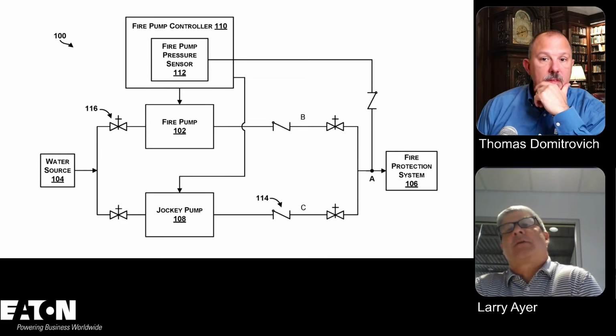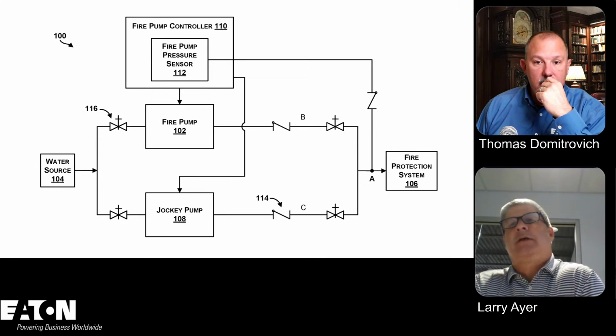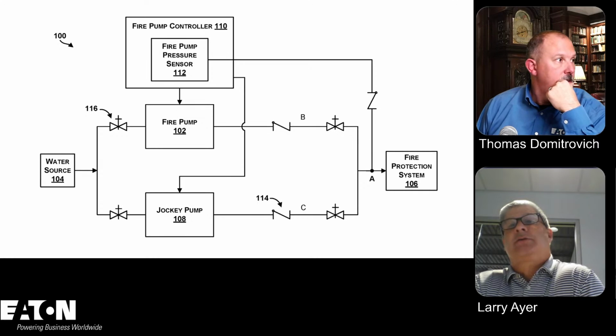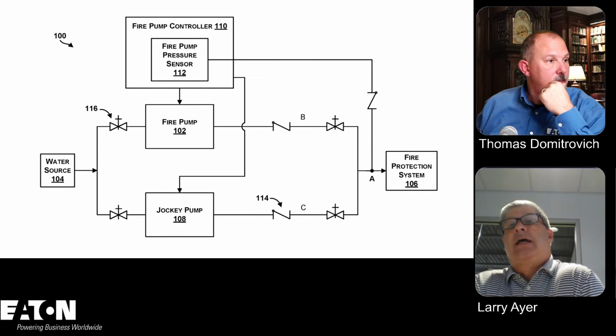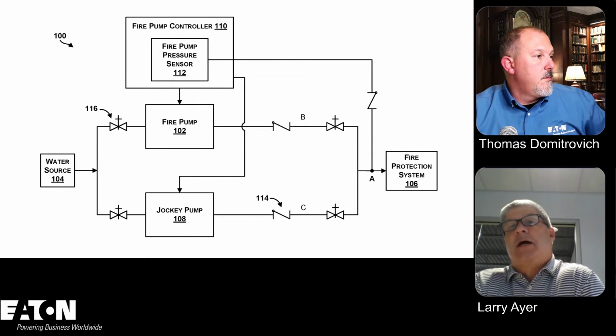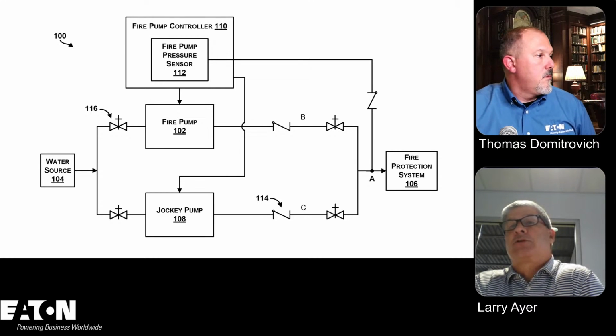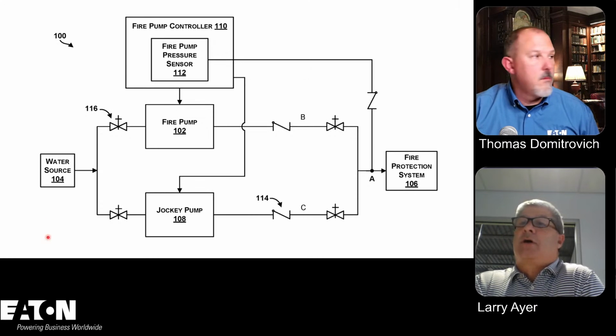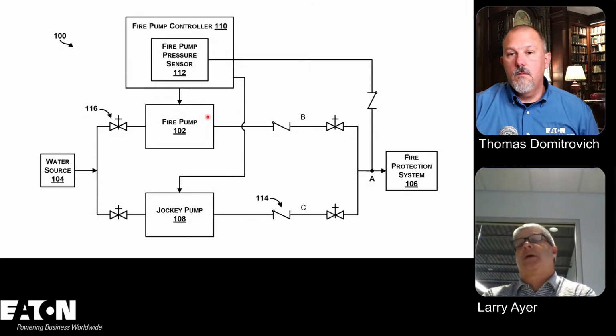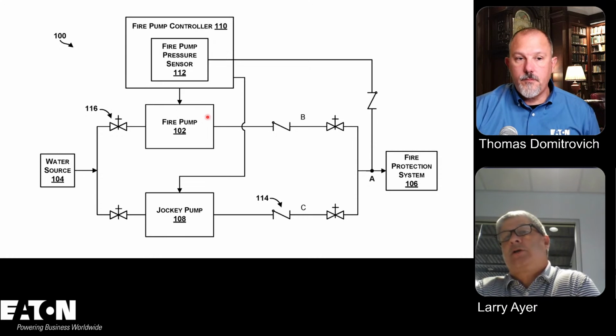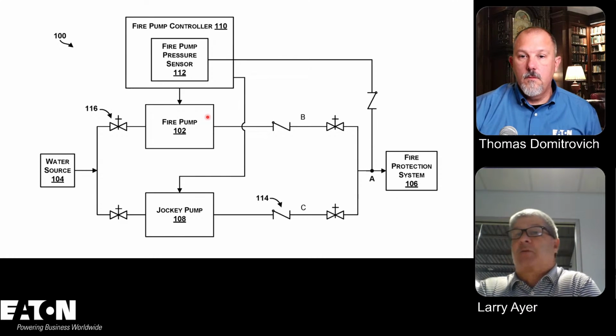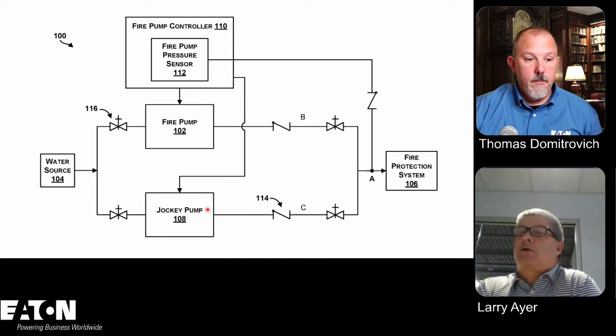Well, this was just to talk about the fire pump and the jockey pump. Typically the fire pump is your lifeblood right there. This is what this whole course is really about. You take your water source, you have a pump there, the fire pump, that pushes the water through the building. Of course, the higher you have to push the water, maybe in a high-rise building, the bigger the pump you have to be concerned with. But you also typically need a jockey pump. It's a smaller water line, and you can see it in parallel, and it's there to maintain pressure in the system.